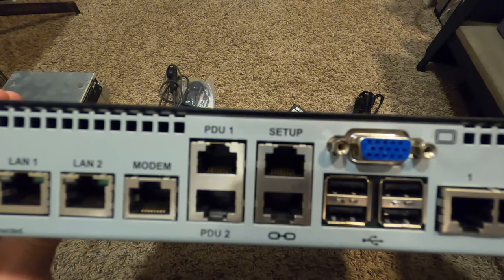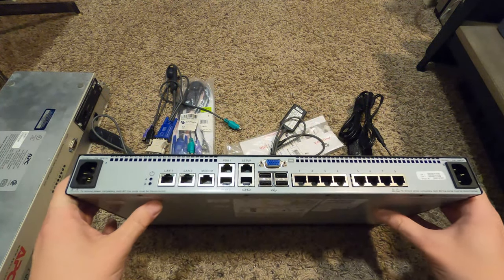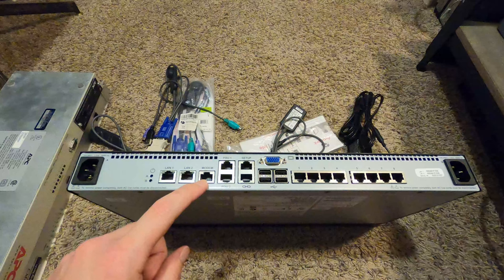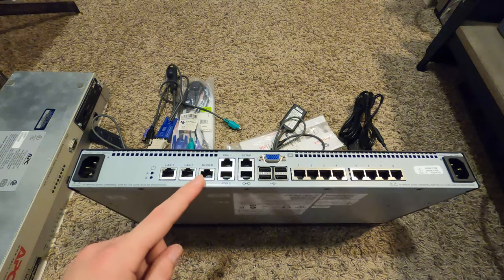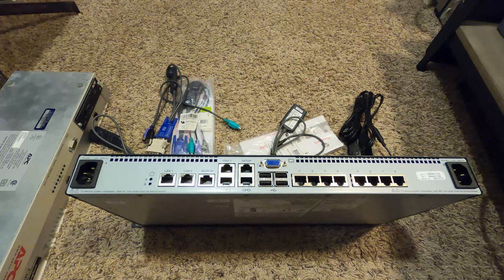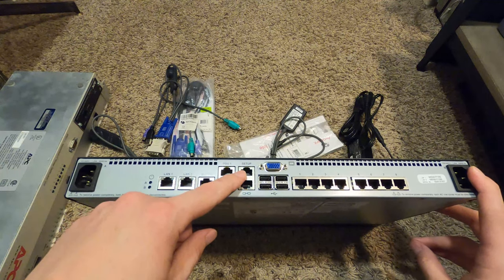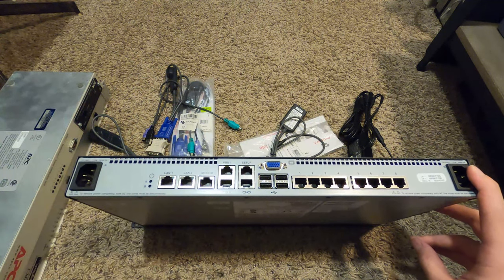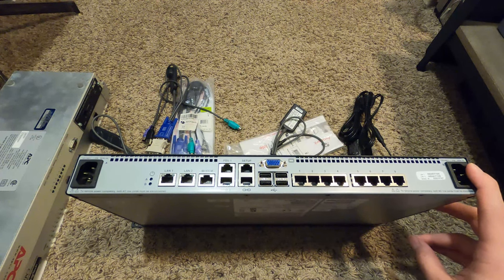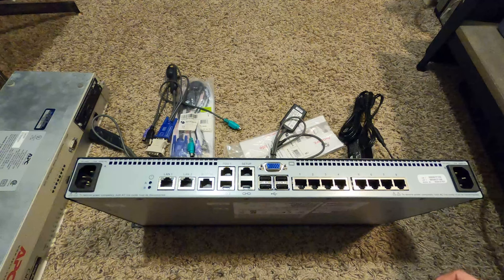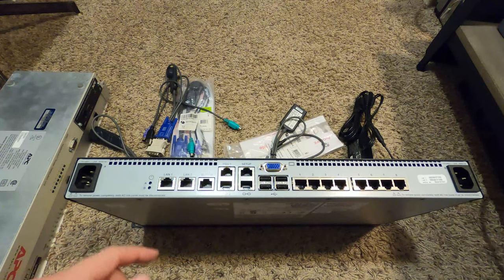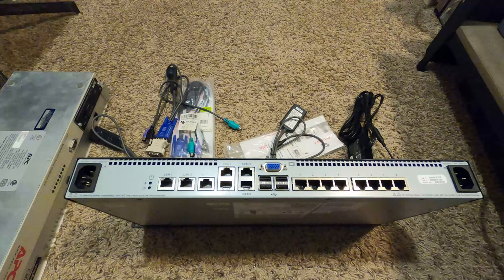Then there's this cluster of modem, PDU1, PDU2, setup, and chain ports - all RJ45 ports. The modem port supports a V.34, V.90, or V.92 compatible modem, probably for console configuration. Similar to this setup port, you can log in via RS-232 and configure it if you don't have physical access or can't get to the web browser.